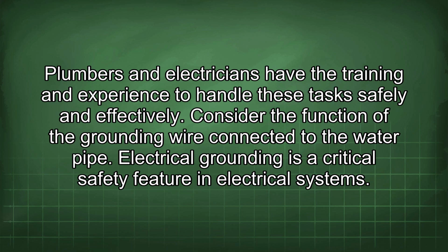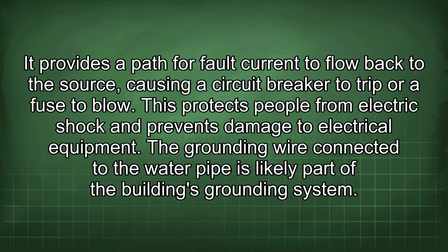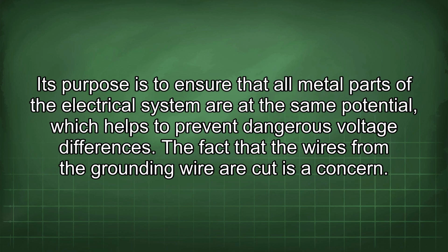Consider the function of the grounding wire connected to the water pipe. Electrical grounding is a critical safety feature in electrical systems. It provides a path for fault current to flow back to the source, causing a circuit breaker to trip or a fuse to blow. This protects people from electric shock and prevents damage to electrical equipment. The grounding wire connected to the water pipe is likely part of the building's grounding system. Its purpose is to ensure that all metal parts of the electrical system are at the same potential, which helps to prevent dangerous voltage differences.